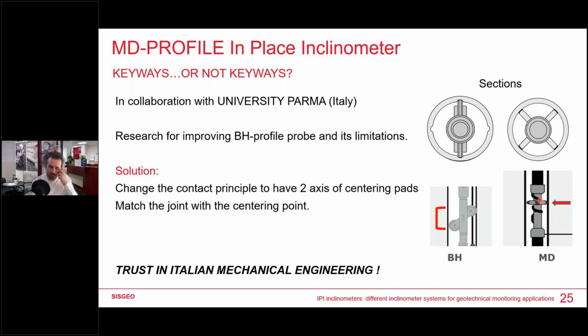Here with the MD profile, the main difference is that you don't have one pair of points touching the tube. You have 4 points, and the 4 points are exactly at the same depth. If you compare with the BH profile, you have a spring wheel, and when you insert it inside the tube, you can have up to 10 centimeters difference between the upper wheel and the lower wheel. With the MD profile, it's completely different. You have only one level of contact between the ground, the tube, and the system. It makes a real difference.